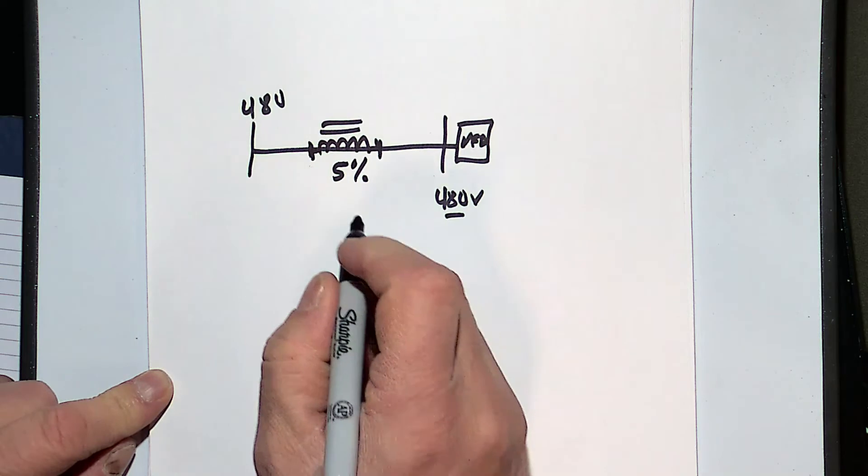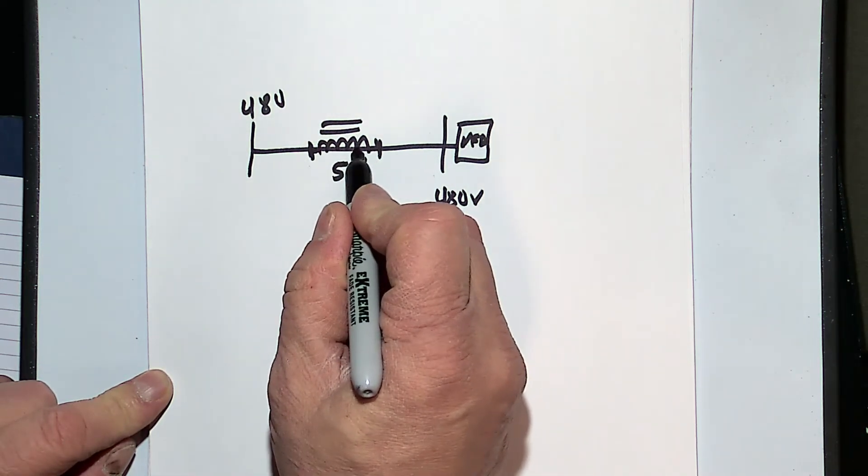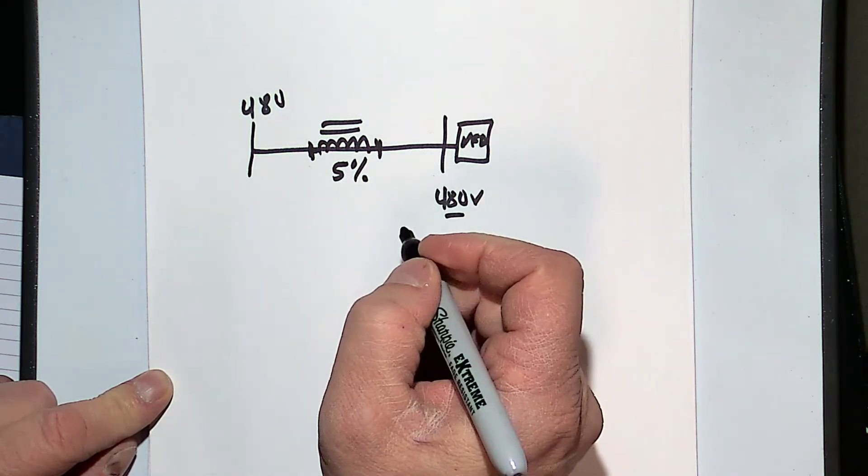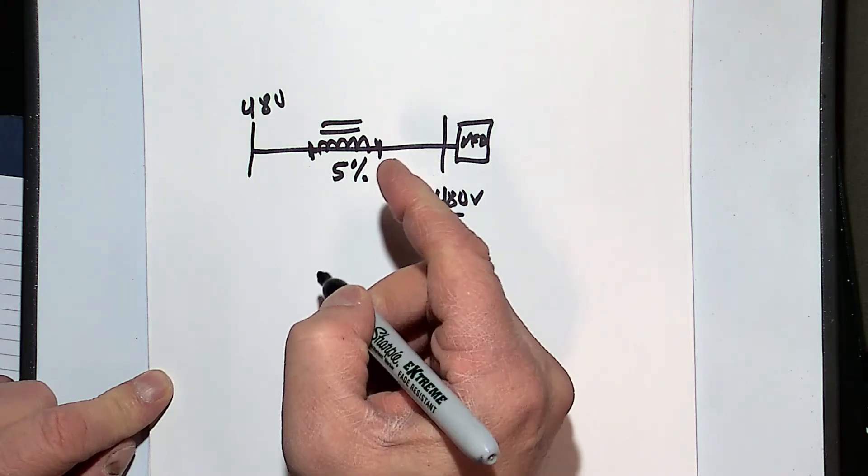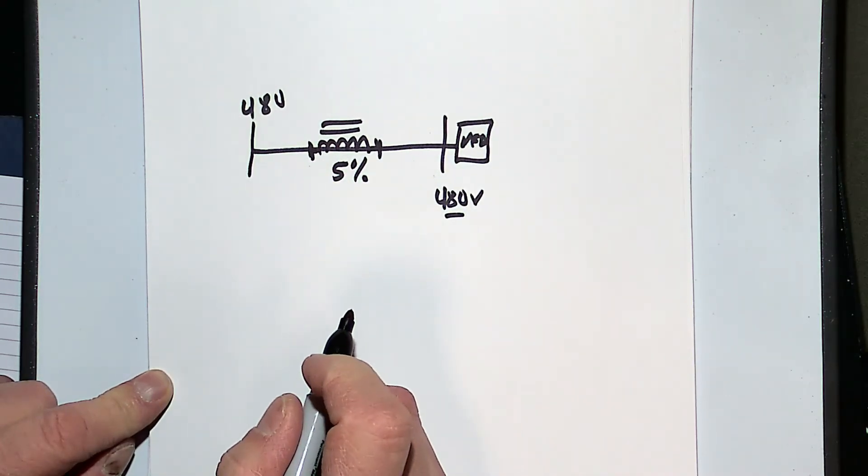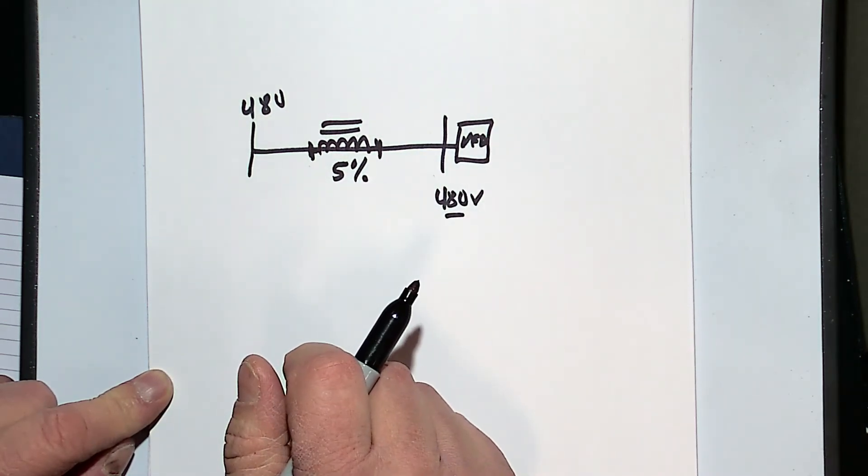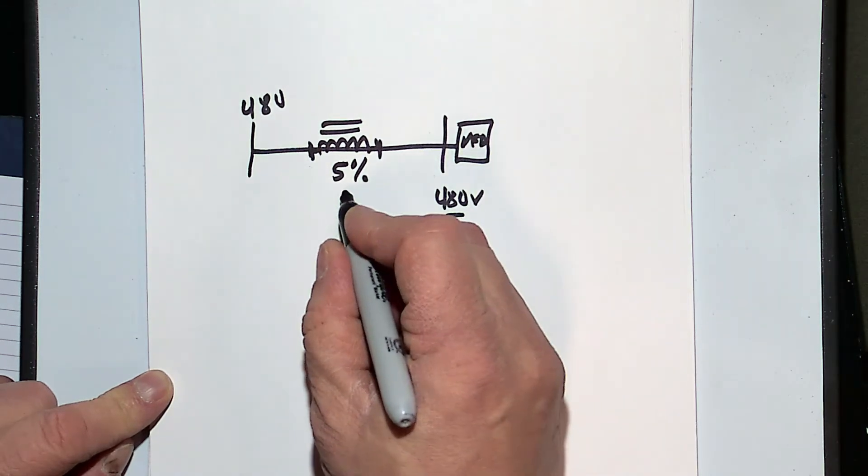What our experience has shown us is that because this is an inductive reactance, and because the load has a high power factor, meaning the voltage and current are in phase, the drop across this reactor is quadrature to the line current that's flowing. So when we multiply those two together, we might get about maybe half of that percent drop, so maybe 2% drop.